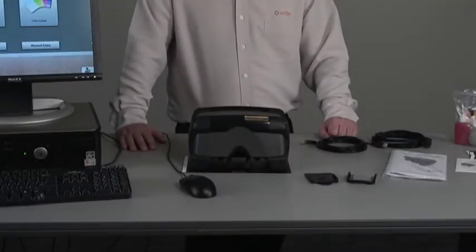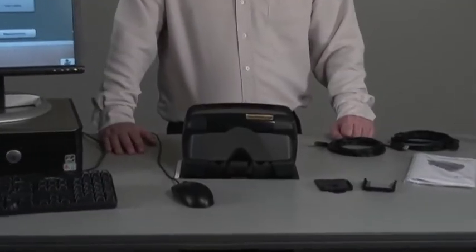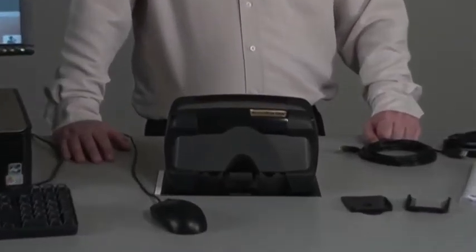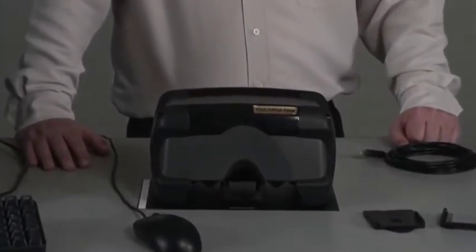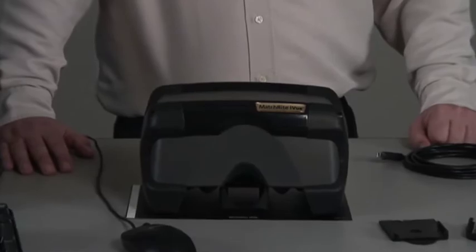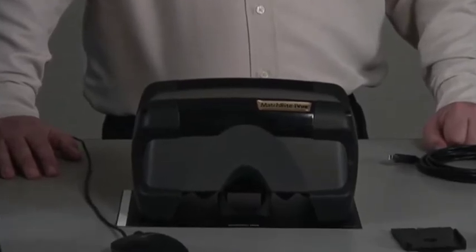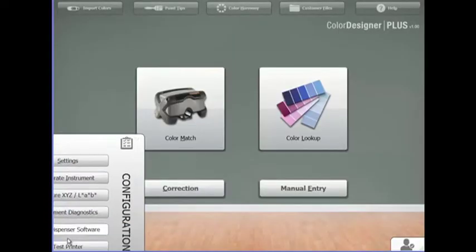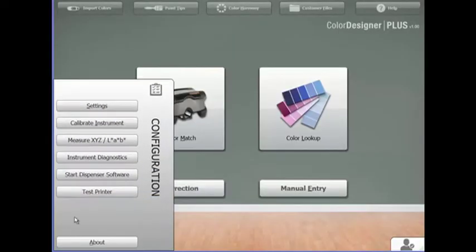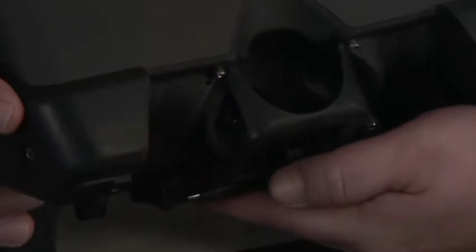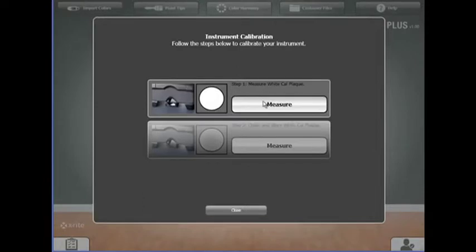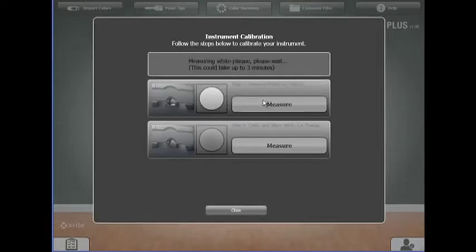The next step is calibration. Calibrating the iView is important and it's only done once a week. Make sure the instrument is clean and dust free. In Color Designer Plus, go to the configuration panel and click on calibrate instrument. Slide the calibration plaque to the forward position. Click on step one, measure.